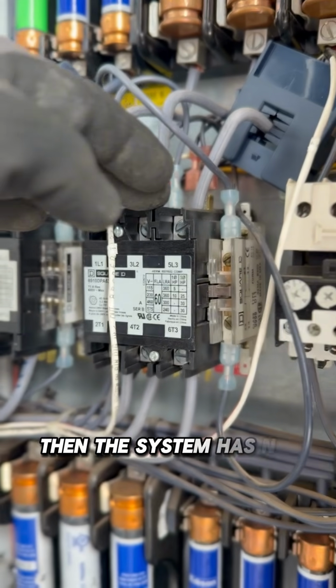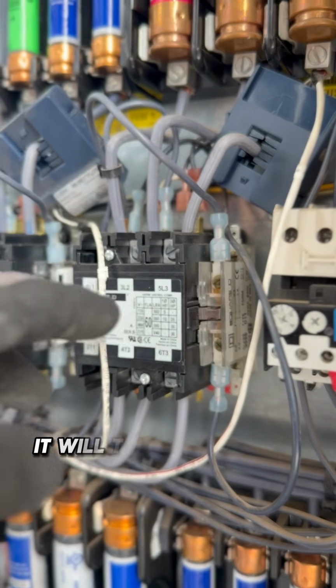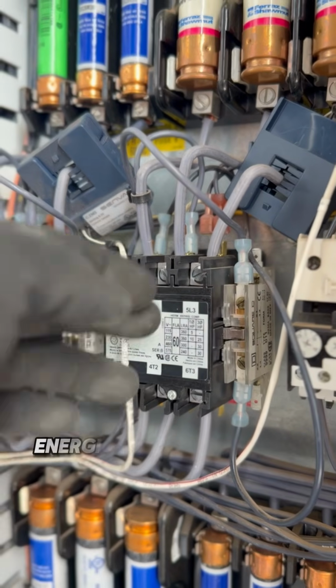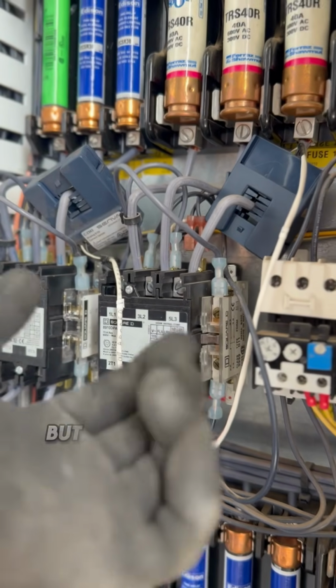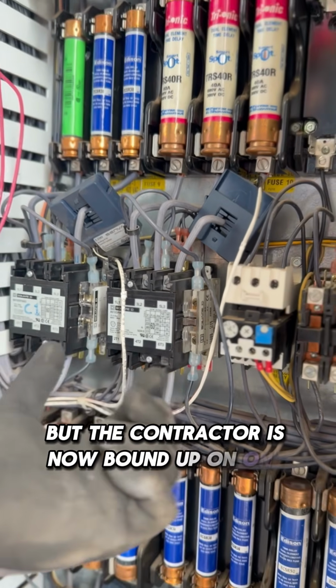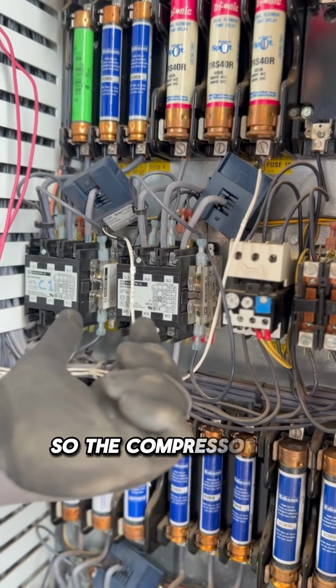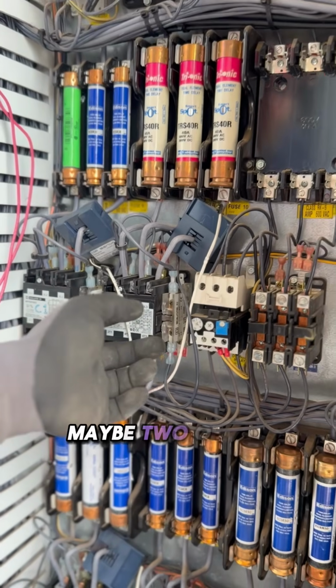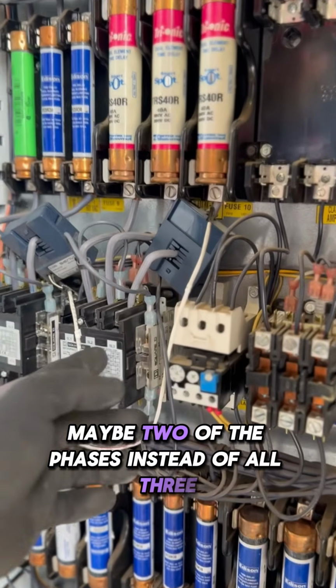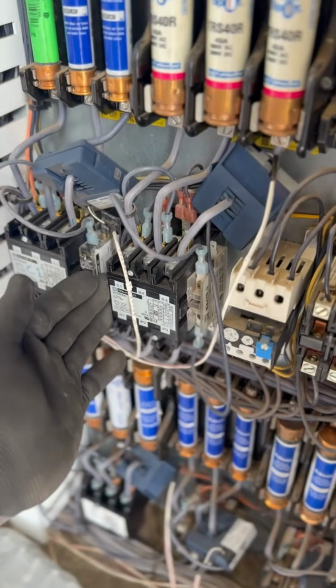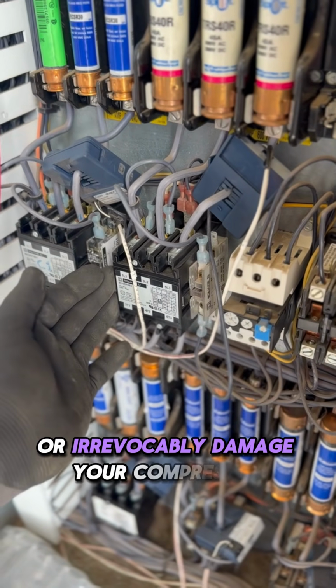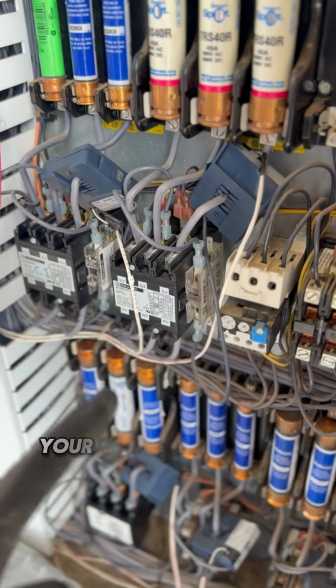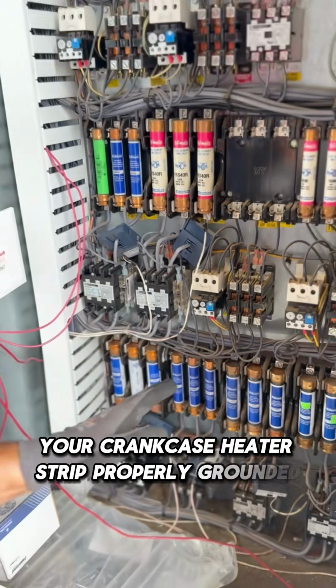Then the system has no idea that happened. It will try to pull in the contactor, energize the compressor for cooling, but the contactor is now bound up on one side. So the compressor is only getting one, maybe two of the phases instead of all three. This could potentially harm or irrevocably damage your compressor, all from not having your crankcase heater strip properly grounded.